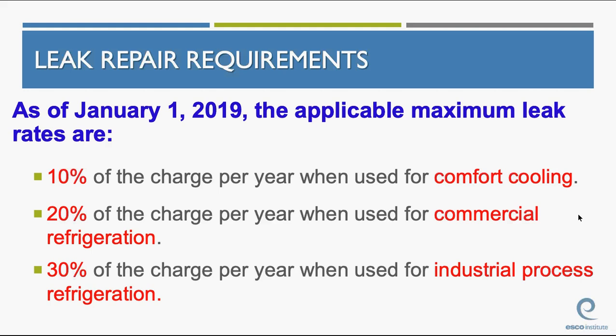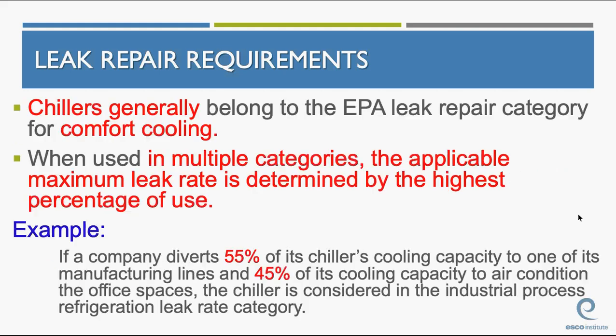As of January 1st, 2019, the maximum acceptable leak rates are 10% of the charge per year when used for comfort cooling, 20% of the charge per year for commercial, and 30% of the charge per year for industrial. This is the same numbers as you have in Type 2. Nothing has changed. Same numbers as you have in Type 2.